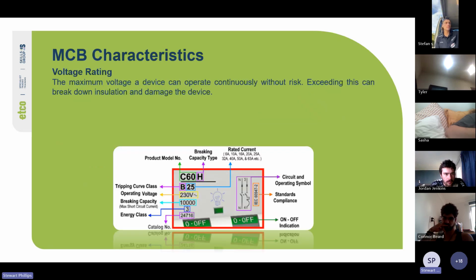MCB characteristics, so voltage rating. That's the maximum voltage a device can operate continuously without risk. Exceeding this can break down insulation and damage the device. The one here has an operating voltage of 230. Its breaking capacity is the max short circuit current it can handle. This one's rated at 10,000, or 10 kA, which is not normal. Normally you'd get 6 kA; 10 costs more. And its tripping curve is class B. It's an HRC, high rupturing capacity type, and it's a 25 amp breaker.